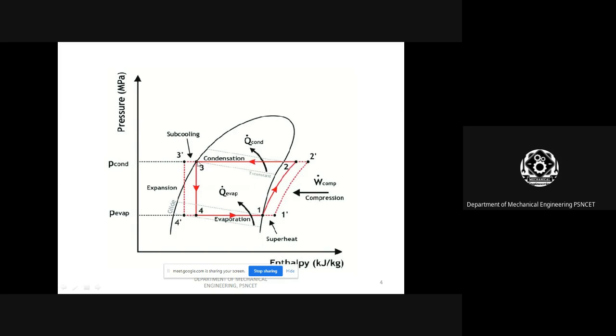From point 3, we expand. Due to the expansion, pressure is reduced from high pressure to low pressure, right? At low pressure, it is a combination of both liquid and vapor. And then from 4 to 1 is the evaporation process. This is the heart of the refrigeration, 4 to 1. Here we extract heat from the body. Due to the heat, the liquid refrigerant is converted into vapor refrigerant, and pressure remains constant till point 1, and then the cycle is repeated.